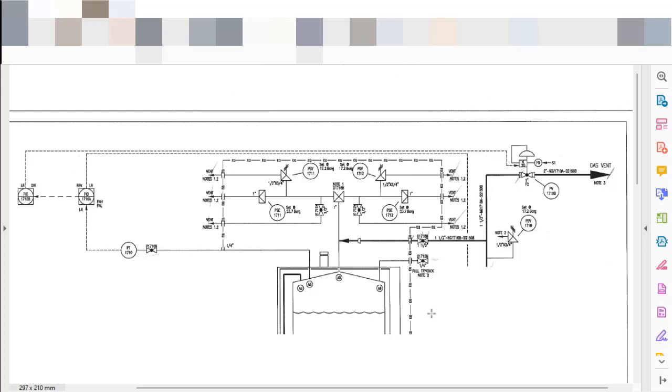In this example, you can see the three types of relief devices. I have a cryogenic fluid inside a vessel, and because of the heat leaking in from the environment, although I have insulation, I can have vaporization of this fluid if for any reason my customer stops withdrawing liquid from the process. As I have no withdrawal of product, my vessel will fill until I reach the maximum level permitted in this equipment, and I will stop feeding cryogenic fluid to this vessel.